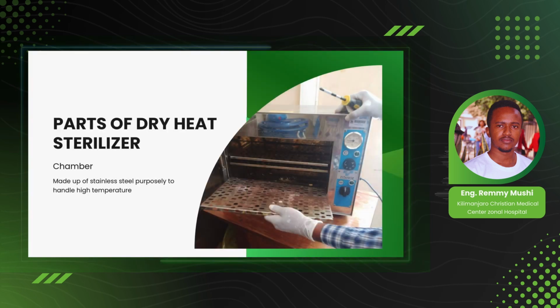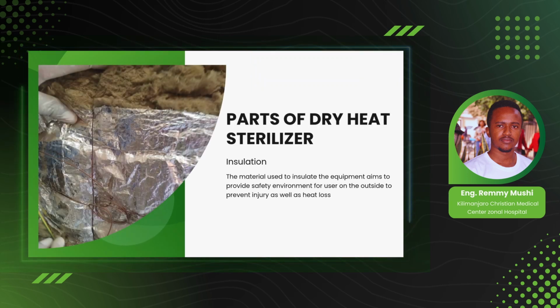The chamber is the hollow volume inside the dry heat sterilizer. This chamber is made of stainless steel because we need the temperature inside to be maintained without much dissipation, and stainless steel can handle this high temperature. The insulation is used to protect the equipment as well as the user from injuries. Without insulation, the user would be open to physical injuries, and the circuitries inside the machine would be exposed to melting or malfunctioning. So there is a need for insulation.